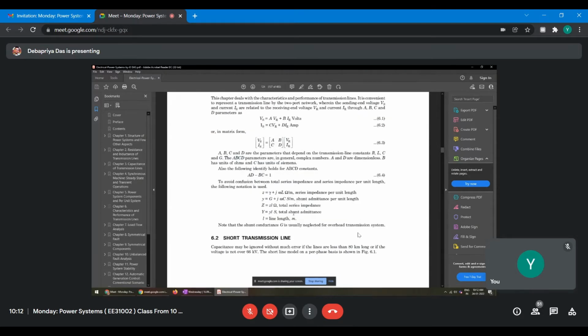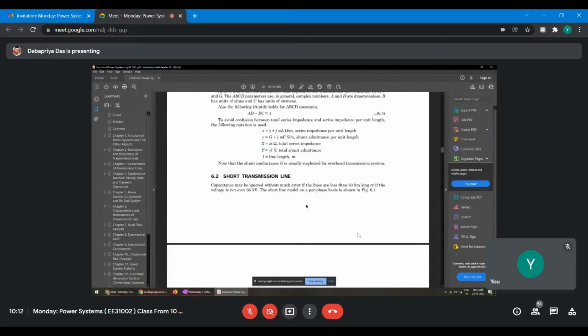Now, short transmission line. Generally, whenever your transmission line length is 70-80 kilometers and the voltage level is low, the charging capacitance is ignored. When studying the capacitance chapter, we assume two parallel plates, one is ground, another is the transmission line. Charging current will flow, and the capacitance is uniformly distributed along the line, with charging current from line to ground due to that line-to-ground capacitance. But if the voltage level is low and the length is less, that capacitance can be neglected. Generally for 33 or 66 kV lines, that is not much prominent.